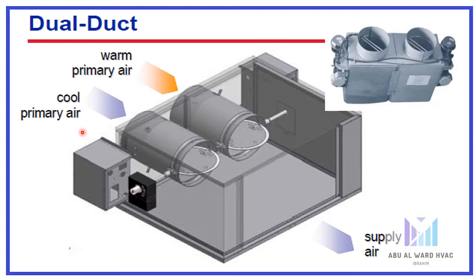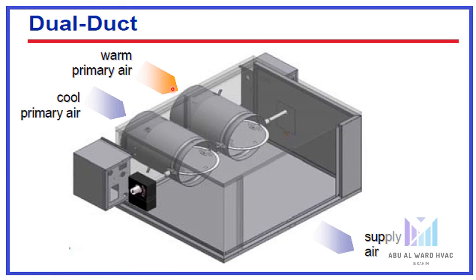Next to the single duct terminal we have the dual duct terminal. A dual duct terminal unit consists of two airflow modulation devices with controls packaged in a sheet metal enclosure. One controls the cool primary air and the other controls the warm primary air. Depending on the method of control, these two air streams may mix in the dual duct unit before proceeding downstream to the space. The VAV dual duct terminal unit is intended for zones that require seasonal cooling and heating, typically the exterior zones of a building. It is seldom used because of the high first cost associated with providing two duct systems.